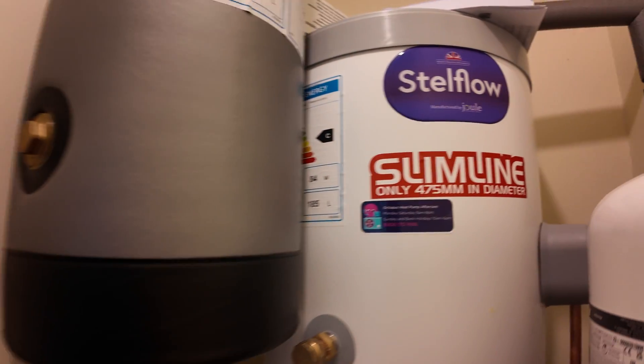It's saying outside is 20 degrees, the floor has come down right to the bottom where it's set at 25 with the maximum at 50. The inside temperature is showing 21 degrees and the water is at 39. It's set to come on a schedule.